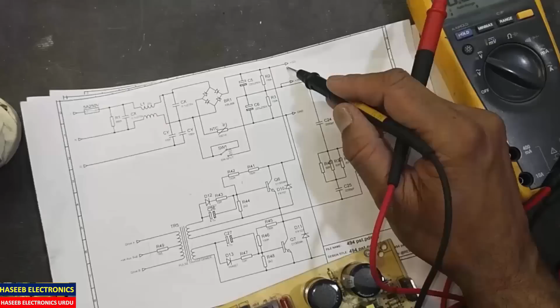If we apply line voltage, we multiply by 1.414 to get the voltage here. This voltage must be divided, and the equivalent voltage we calculated should be available at these two capacitors. If we don't find that voltage, or we find a big variation, it means these capacitors are internally open or their ESR value has risen, so they can't store the charge properly. In that case we replace these capacitors — it's a very common failure.